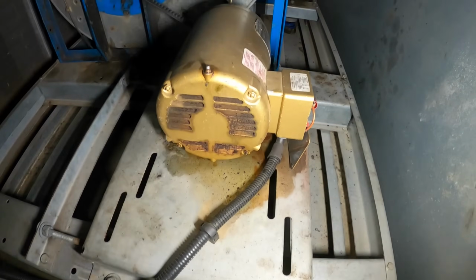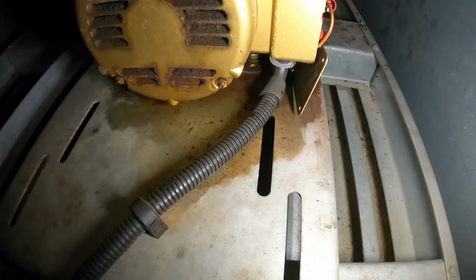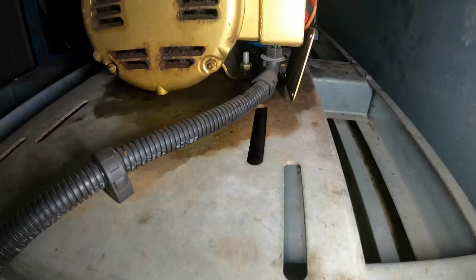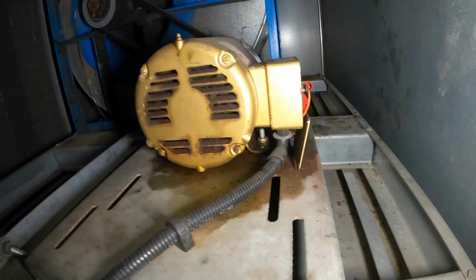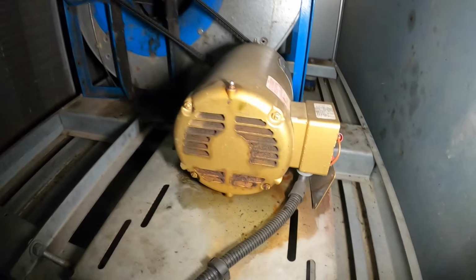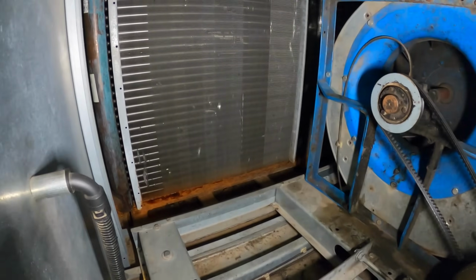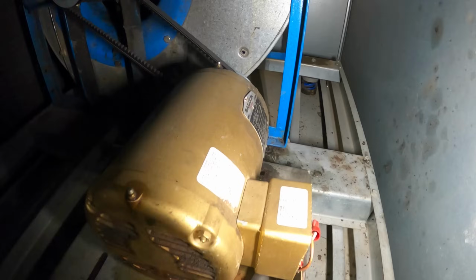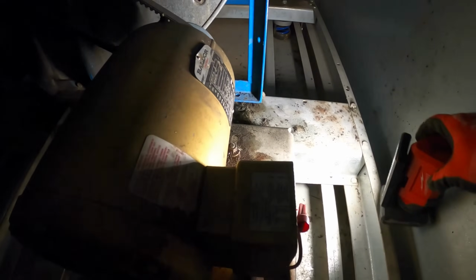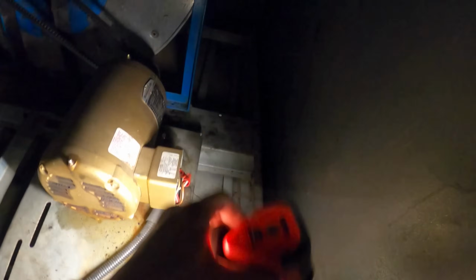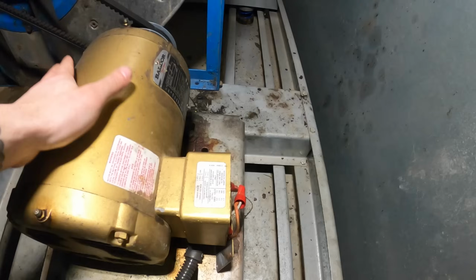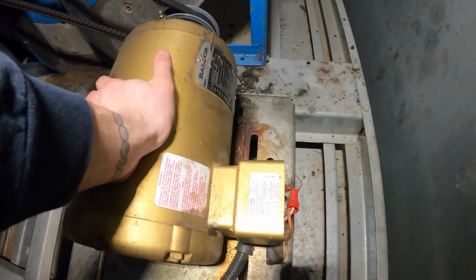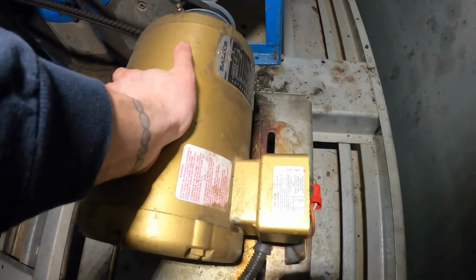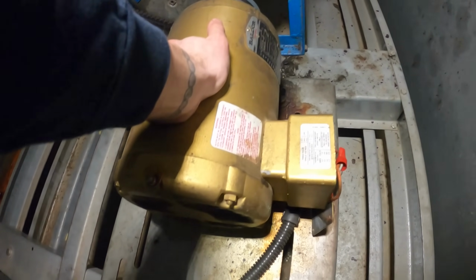Look at that stain. What is all that? Is that oil or something? Maybe grease was coming out of that motor. It's like somebody was messing around in here already. They don't know what's going on. Maybe the valve is open, that's why there's heat. It's an old Baldor motor. You know what? Motor's not hot. It was never getting power.